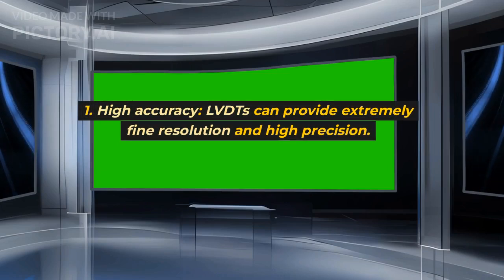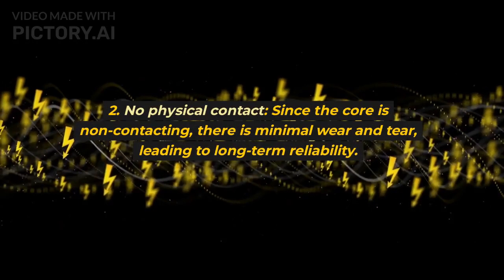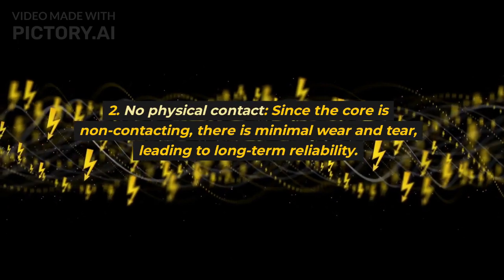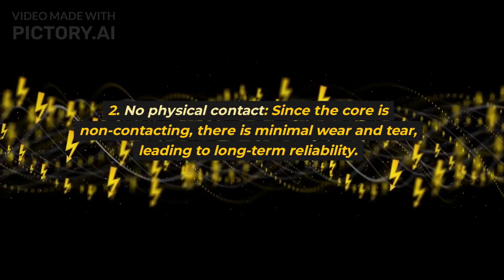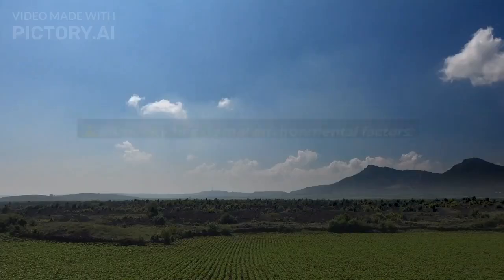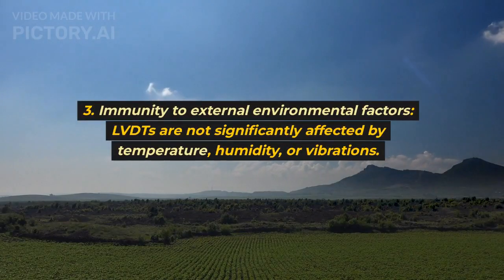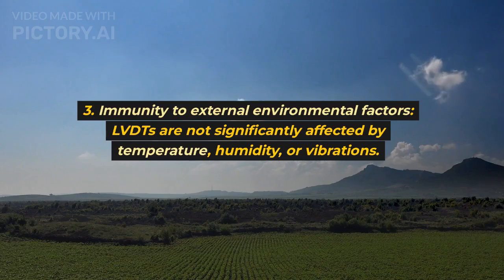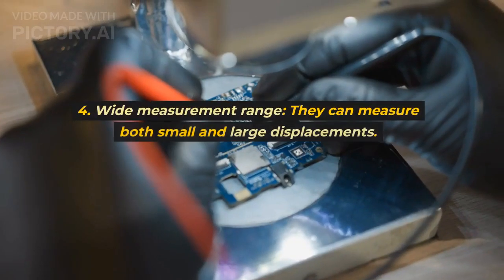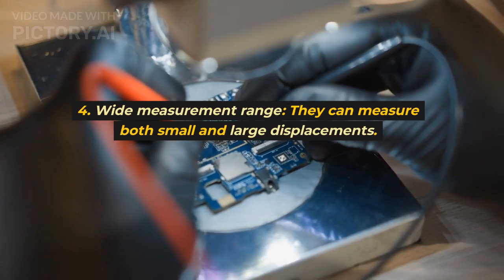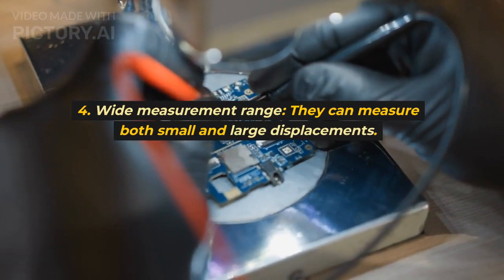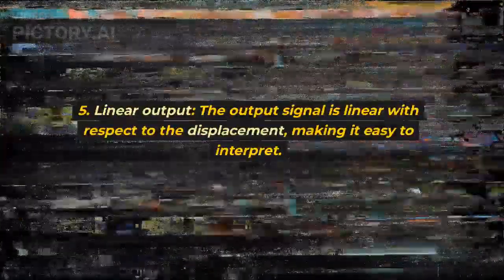High accuracy. LVDTs can provide extremely fine resolution and high precision. 2. No physical contact. Since the core is non-contacting, there is minimal wear and tear, leading to long-term reliability. 3. Immunity to external environmental factors. LVDTs are not significantly affected by temperature, humidity, or vibrations. 4. Wide measurement range. They can measure both small and large displacements. 5. Linear output. The output signal is linear with respect to the displacement, making it easy to interpret.